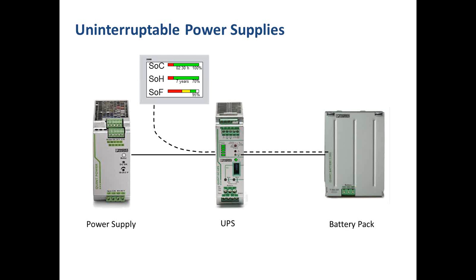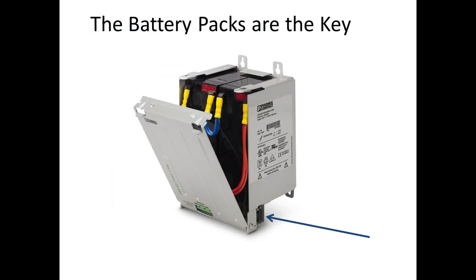Our last area of interest is uninterruptible power supplies, or UPSs. Newer industrial UPS technology has intelligence to present the battery's state of charge, remaining backup time, percent of life expectancy, and many other variables. There is also a battery charge display for at-a-glance information. The intelligence of the UPS is based on its ability to communicate with the battery pack. These battery packs have an internal electronics module, and in the diagram, that's where the arrow is pointing at the electronics module. The battery packs can communicate their temperature, charge, lifetime, and internal resistance, for example. For a smart UPS application in a remote area, an alarm is commonly set for 20% of the remaining lifetime. This alarm ensures that the battery is not replaced too soon or too late.